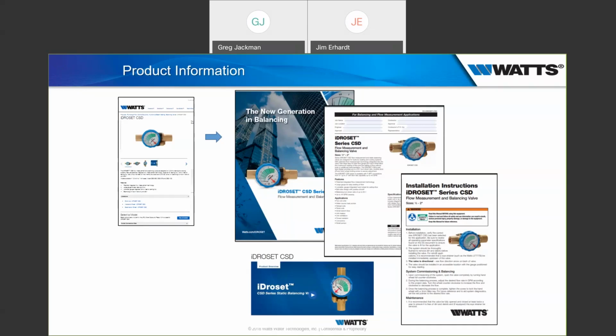You're going to simply set the valve so that you have proper return rate on each one, and that the temperature is balanced between all of your various return legs. And then when that temperature kicks up to 168, it's not going to make any difference. You're going to get the same flow at 168 or 165 that you'll get at 120 or 130, whatever you have your recirc line set up for. So that's the main advantage of the iDROSET: it's not going to interfere with or compromise the sanitization cycle. And number two, if for some reason you decide you have to change the return temperature on the system with those temperature actuated valves, you actually have to change the valve because they come set for one temperature.